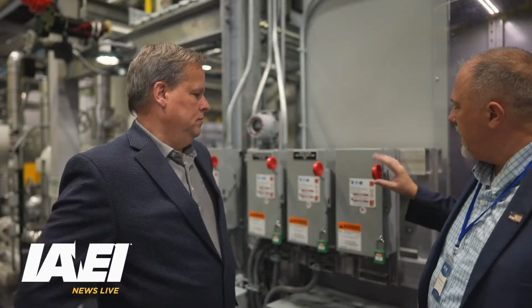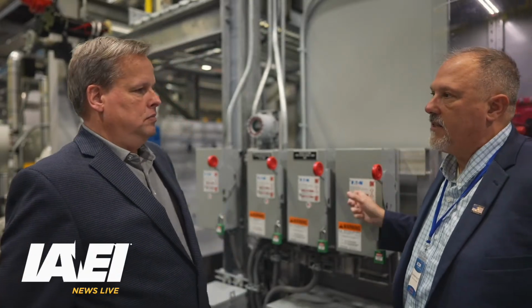Depends on where the circuit breaker is. Circuit breakers, in fact, qualify as a disconnect for motors. Exactly. Because they're rated to manually interrupt 6 times their rating. That's right. So if you have a 100 amp breaker, when you're using it manually, not automatically, that's where the other ratings come into play. A 100 amp breaker can manually interrupt 600 amps.